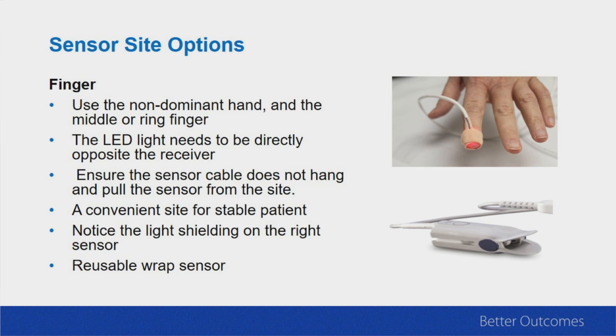So on a sensor like this, that is not a one-piece unit like the bottom unit, you have to take care of that. And I have had a pulse ox manufacturer tell me that the reason we got a bad signal was because the sender and the receiver were off by a millimeter. Just got to be perfect. And not what we've ever been 100% of the time in healthcare, right? But never spent that much time lining up a pulse ox sensor. But that's what they tell you got to do, is line those up. And obviously you're going to get your best reading that way.